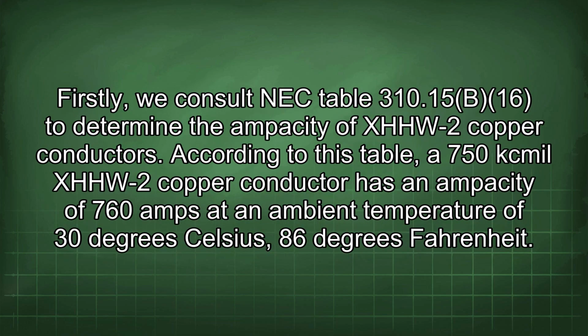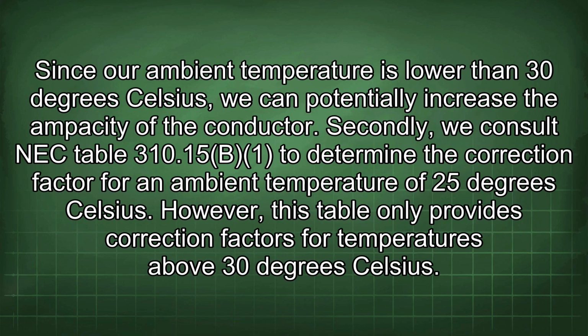Firstly, we consult NEC Table 310.15(B)(16) to determine the ampacity of XHHW-2 copper conductors. According to this table, a 750 kcmil XHHW-2 copper conductor has an ampacity of 760 amps at an ambient temperature of 30 degrees Celsius, 86 degrees Fahrenheit. Since our ambient temperature is lower than 30 degrees Celsius, we can potentially increase the ampacity of the conductor.